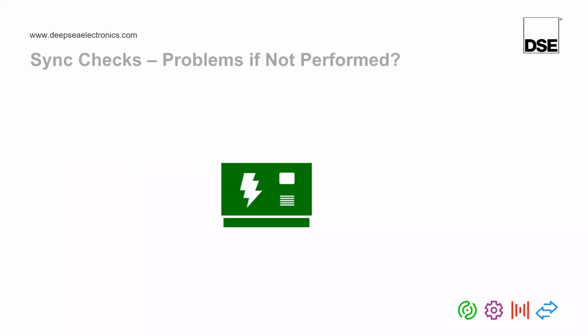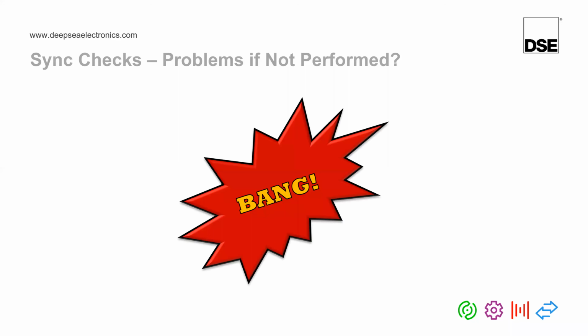If you do not do this check, what could happen? Well, you can clearly see that it could end up with the generator closing out of sync. If a generator closes out of sync, unfortunately, it goes bang. So it's very, very important that you do these phase rotation checks. But if we just go back and remember, you'll see that for step number 1, step number 2, and step number 3, if you did not perform those tests, they all had a very common fault, which was unstable, incorrect, unworking load sharing.